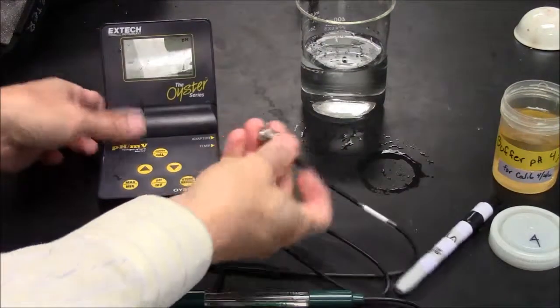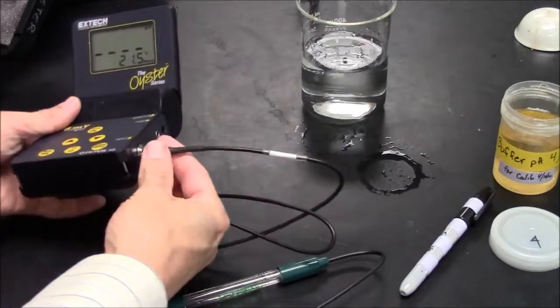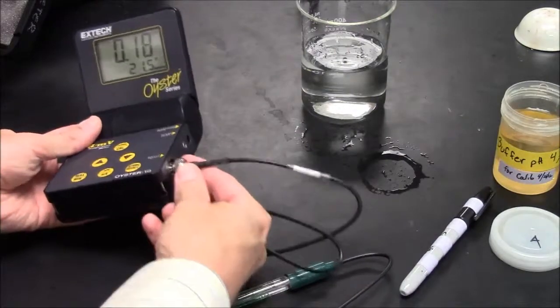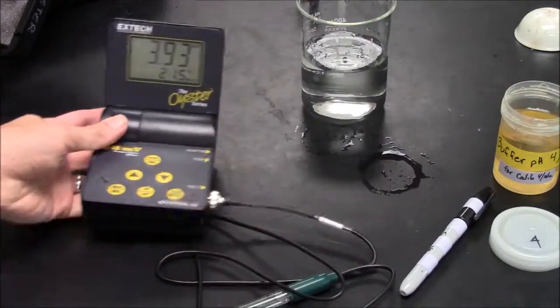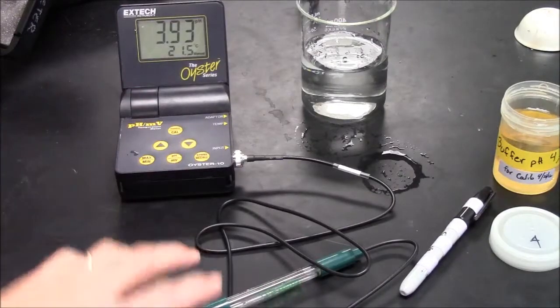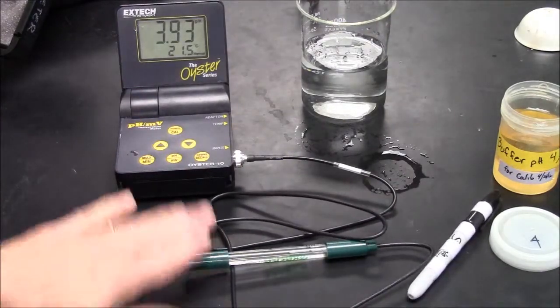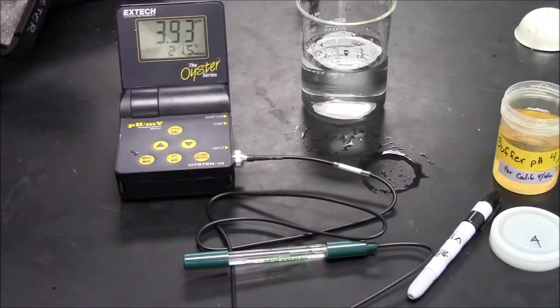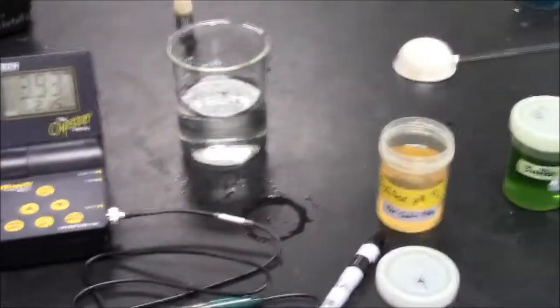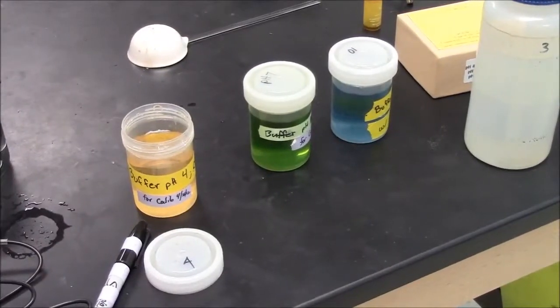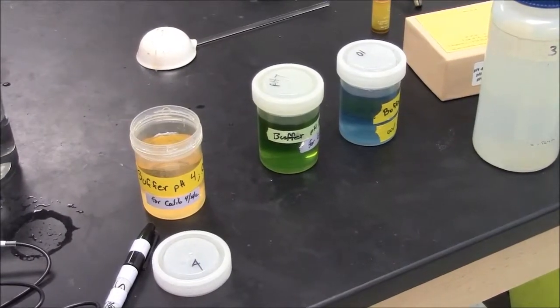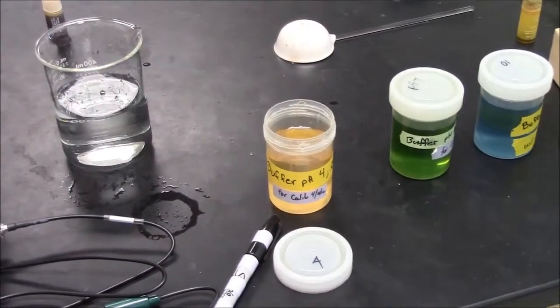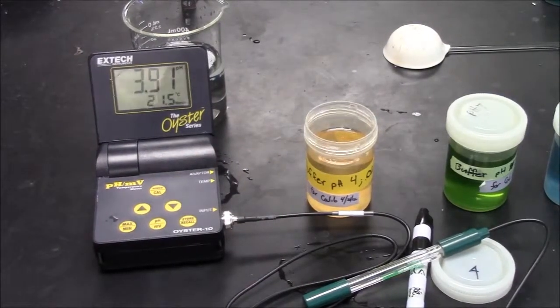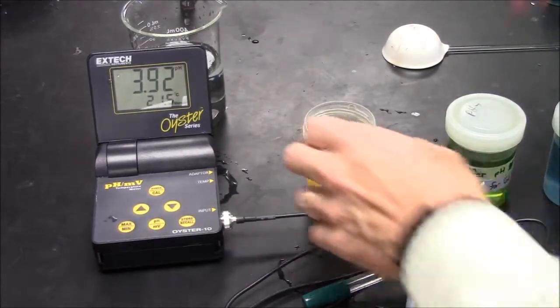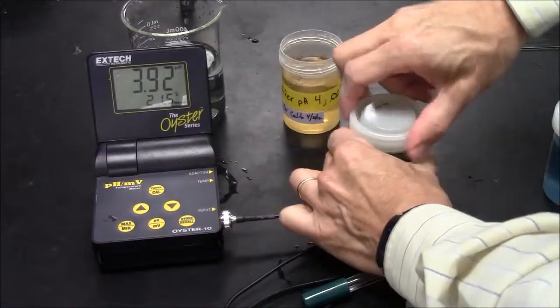Initially, you need to connect the electrode to the pH meter. Push in and turn. If the electrode has been stored properly, the pH should be around 4, as you can see it is. Now I have 3 calibration buffers, pH 4.0, 7.0, and 10.0, and I will calibrate the meter. I can start with any one of these buffers. I will start in this case with a pH of 7.